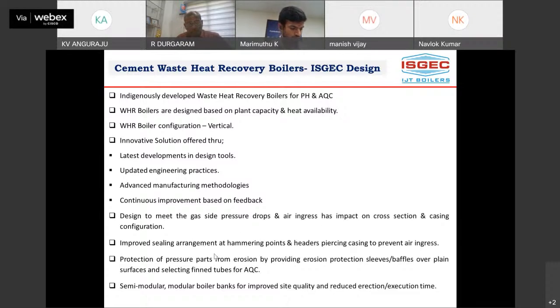So in principle, we say improved sealing arrangement at the hammering points. We call it a double sealing arrangement for the hammer, that is one sliding part where there is likely air ingress into the system, and that is being addressed. And protection of pressure parts from erosion by providing erosion protection sleeves. See, one is the sleeves, another one is the baffles. In addition, if we come to the AQC boiler, we'll be providing sacrificial tubes of the same material. The material selection varies based on the temperature we select, sometimes T12, sometimes T22 also. Whereas for the baffles and other parts, we go straight for stainless steel, which has very good erosion protection properties.